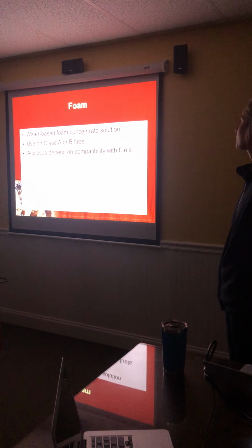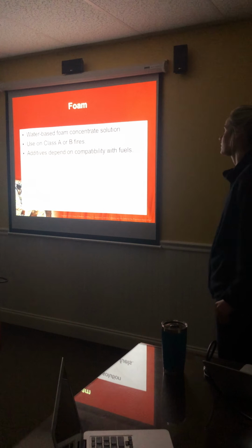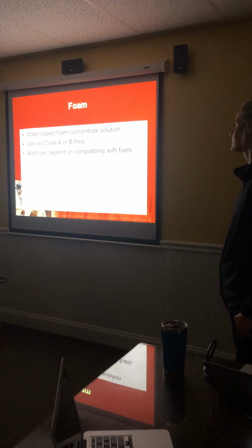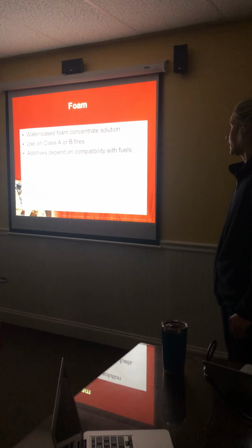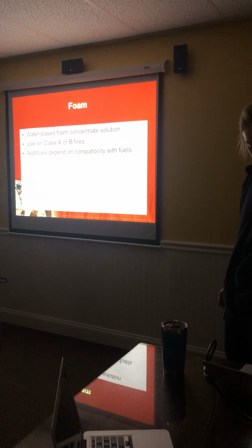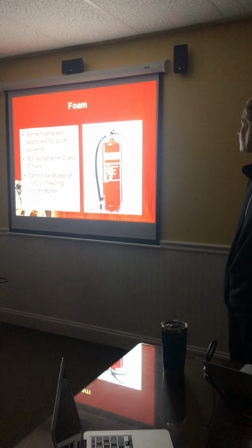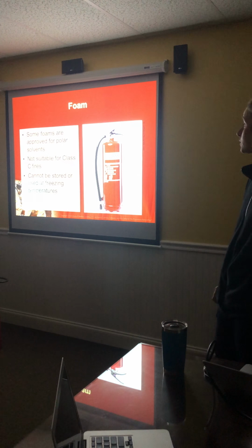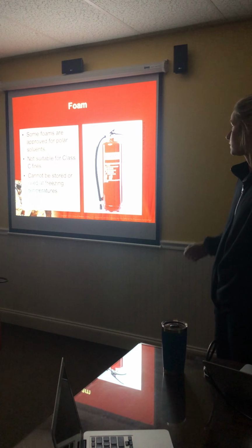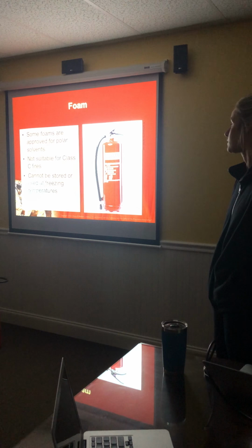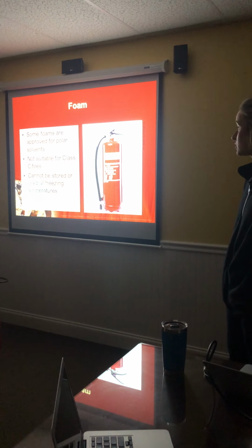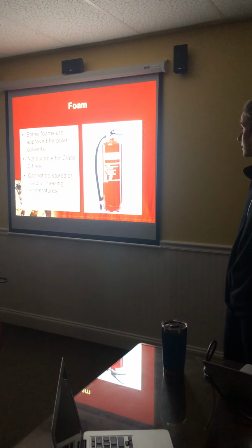Foam: a water-based foam concentrate solution used on Class A or B fires. Additives depend on compatibility with the fuels. Some foams are approved for polar solvents. They are not suitable for Class C fires, and also cannot be stored or used at freezing temperatures.